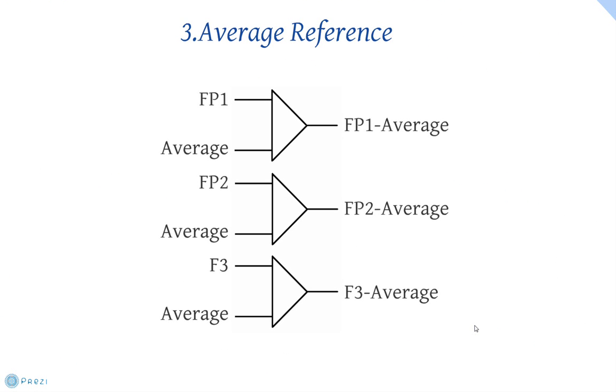A third and final approach which is commonly used is an average reference. Each electrode is passed into an amplifier along with a signal which is an average of all the electrodes currently being measured. This has the benefit of providing an almost constant reference signal, thus allowing us to measure the amplitude of the signal as well as negating much of the interference.